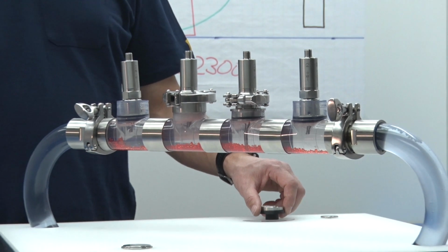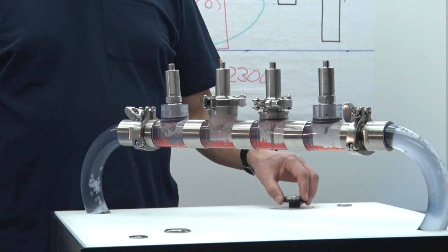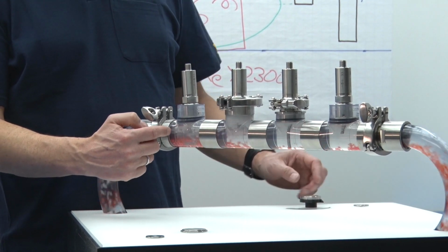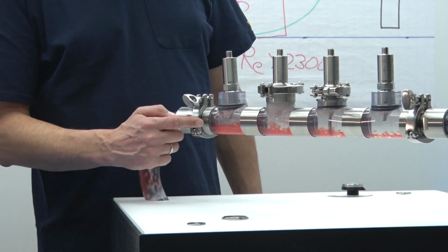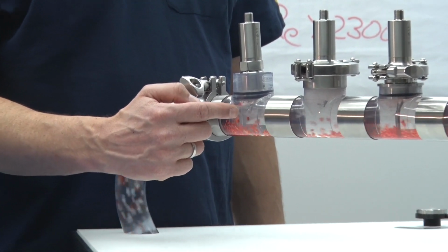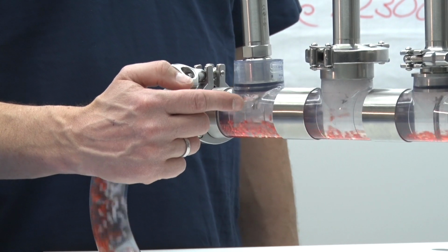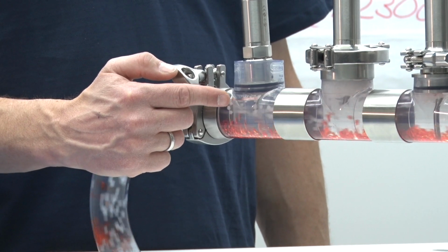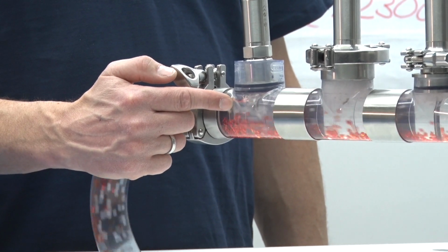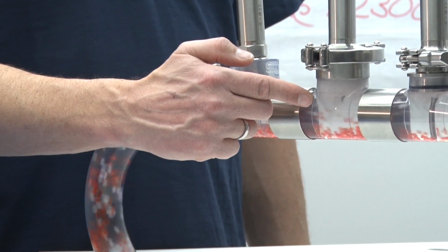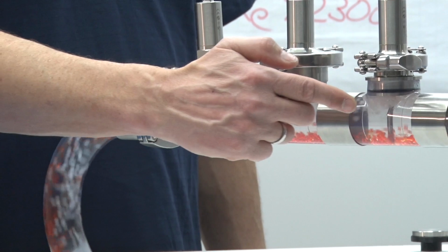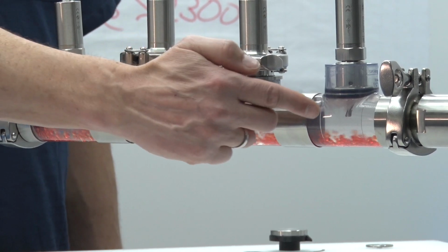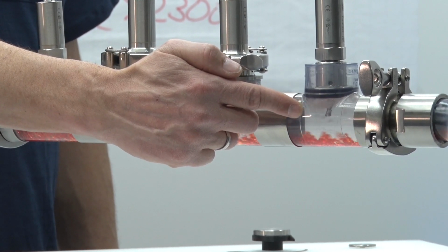In our model, I can switch the flow on here, and you see the laminar flow. Here you see laminar flow. The little spheres inside the pipe are all in the same flow. Consequently, different installation positions will provide different measured results. In this position, the sensor measures average flow. Here, the sensor tip is close to the pipe wall, meaning zero flow. Neither in this position. And finally, maximum flow measured in the center.